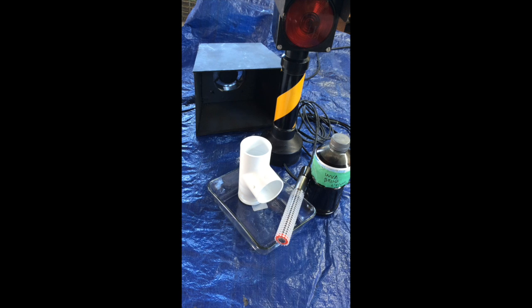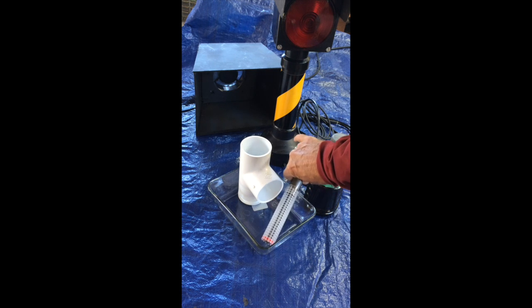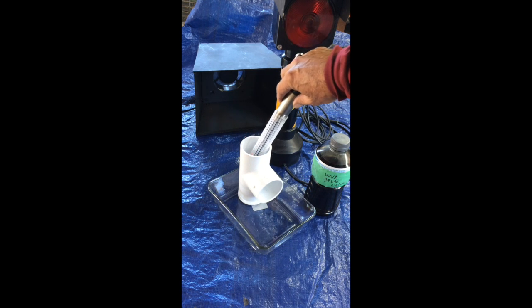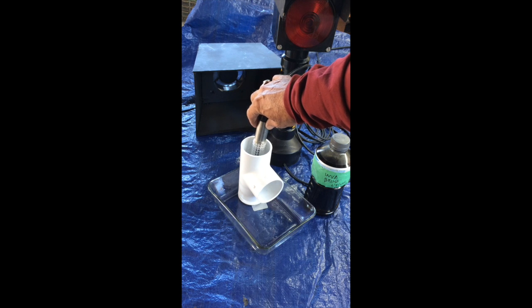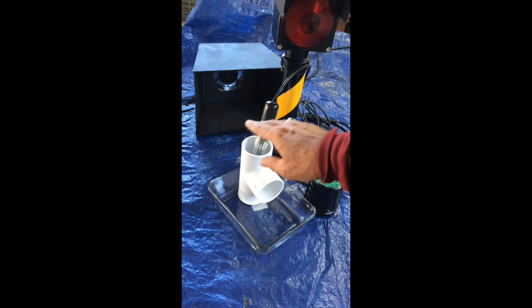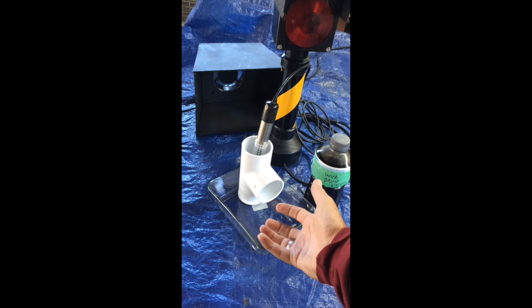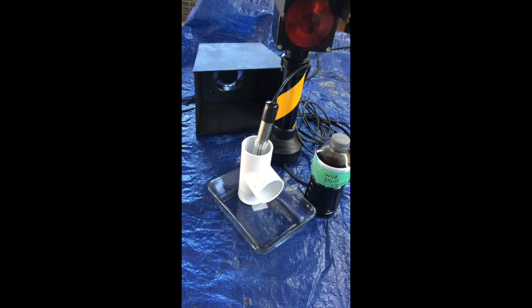There's a PVC fitting, a T-fitting, that is typical of the type used in the under-tank leak detection system, and the probe itself is positioned vertically into the PVC fitting so that any fluid leaking out from underneath the tank would enter the T, fill up the cavity of the T that's capped off at the bottom, and then eventually leak out the side fitting that you see there.